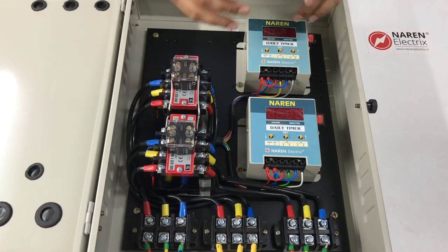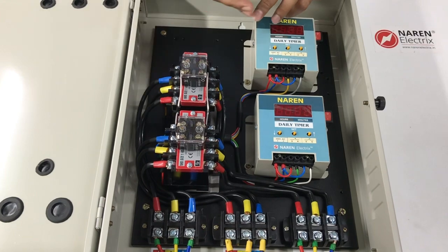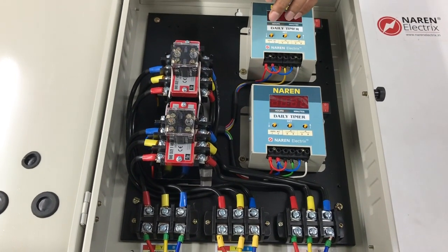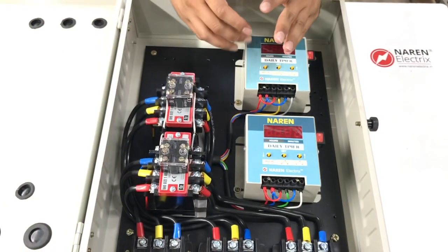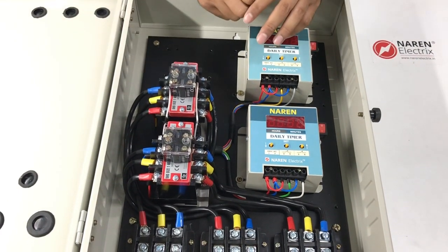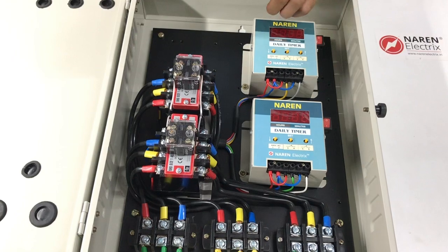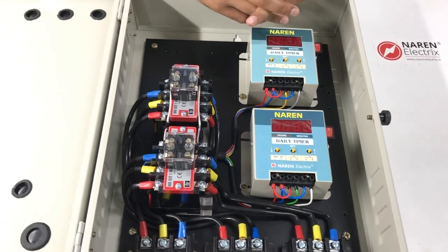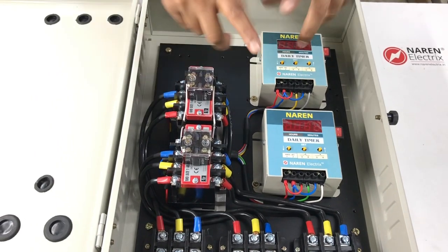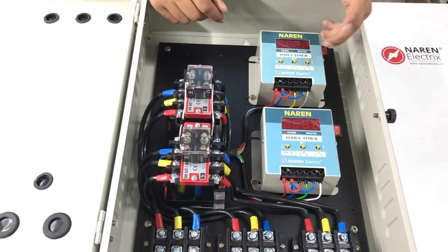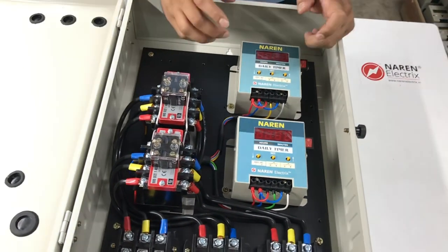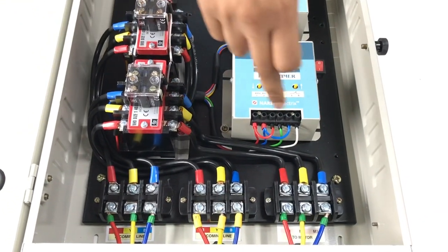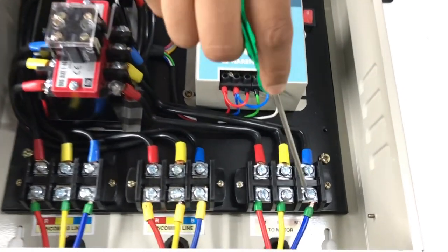One meter is a commercial electric meter, and the second one is a domestic meter. But the load is common. What he's doing right now is physically using a changeover, switching between the commercial meter and the domestic meter. His requirement was an automatic system which will automatically change over between the two meters. The load connected here is three motors, and the load will be connected to this particular point.